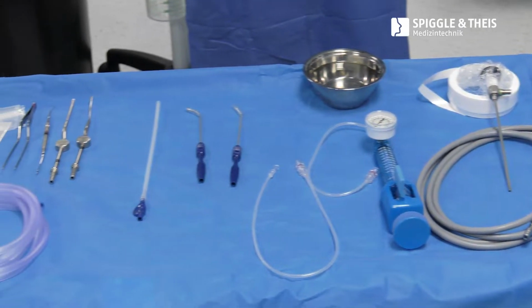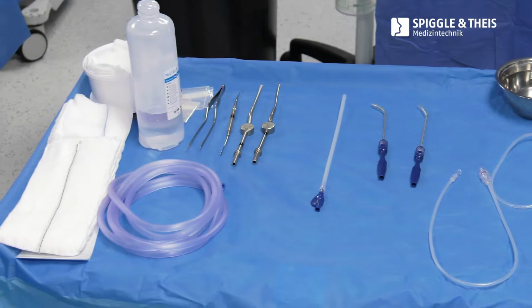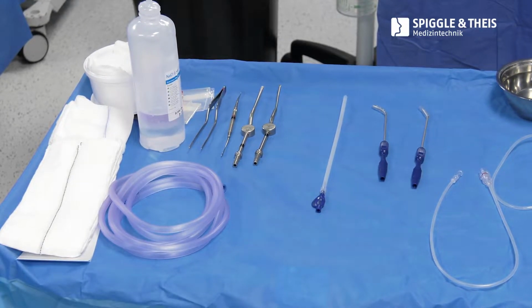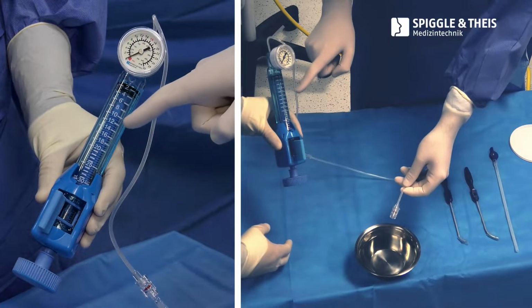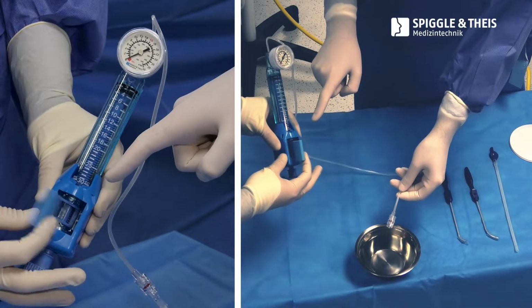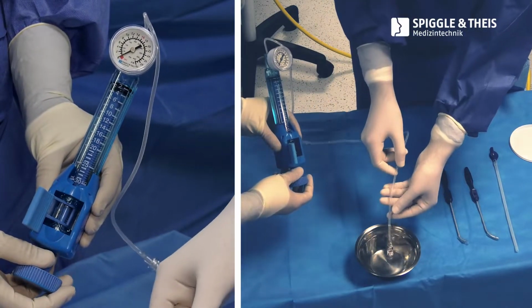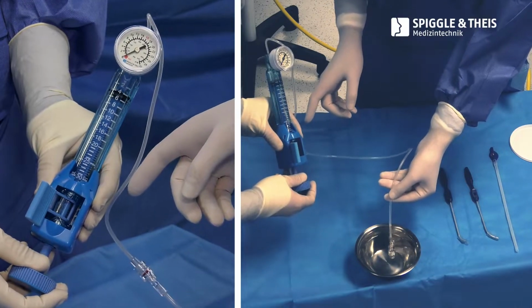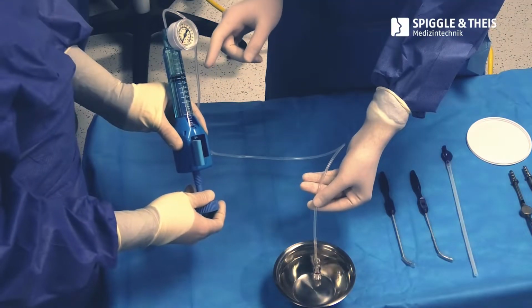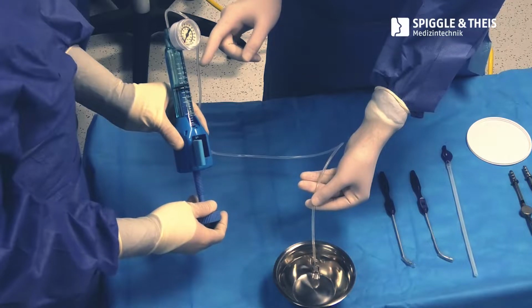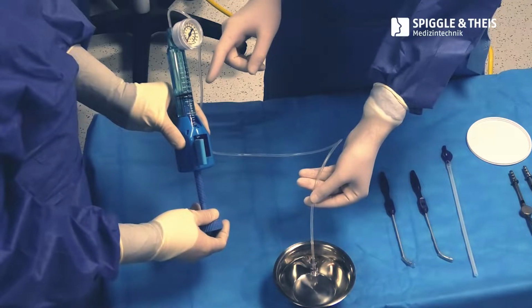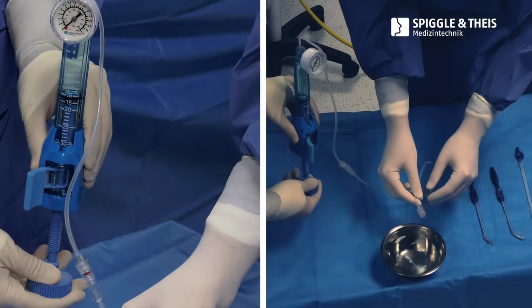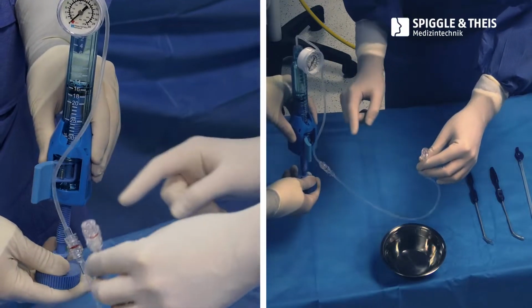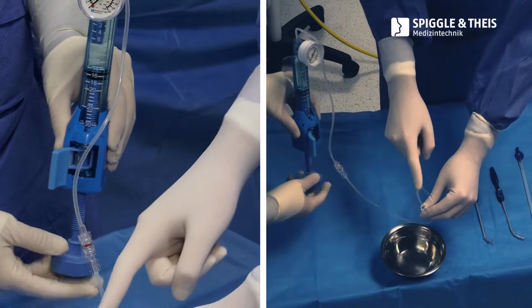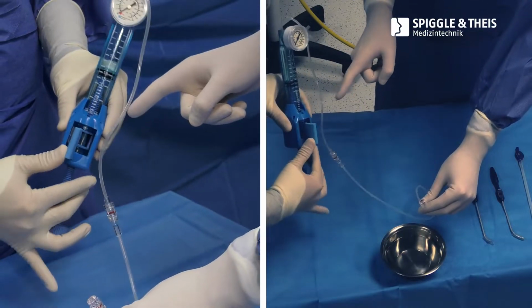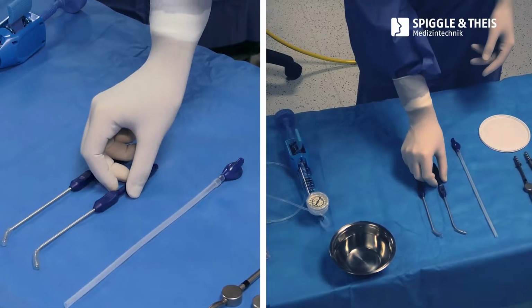The kit also includes an insertion instrument of 70 degrees that we will mainly use on small children. Unblock the pump by sliding the locking lever sideways and fill it with saline solution. Slowly pull the plunger as you would with a normal syringe, trying to prevent air from entering the system. Once the pump is full, the system must be purged so that no air is left inside it. Lock the pump again by sliding the lever back to its original position.